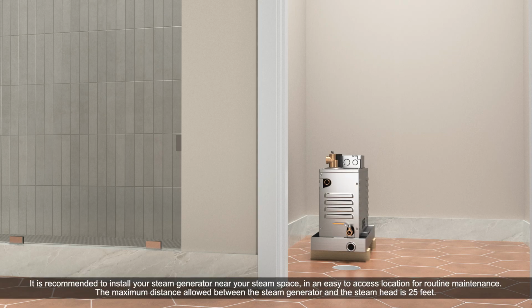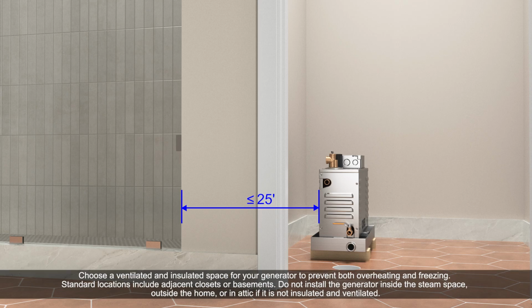It is recommended to install your steam generator near your steam space, in an easy-to-access location for routine maintenance. The maximum distance allowed between the steam generator and the steam head is 25 feet. Choose a ventilated and insulated space for your generator to prevent both overheating and freezing. Standard locations include adjacent closets or basements.